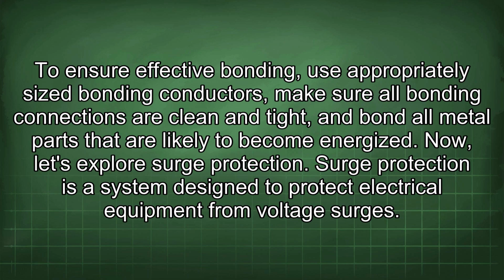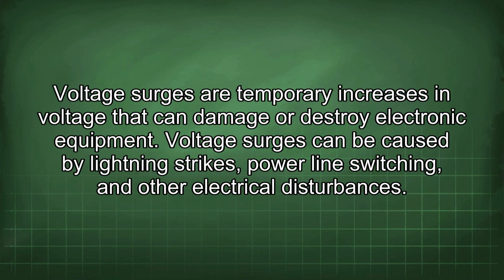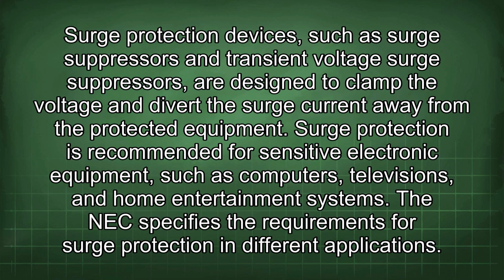Now let's explore surge protection. Surge protection is a system designed to protect electrical equipment from voltage surges. Voltage surges are temporary increases in voltage that can damage or destroy electronic equipment. Voltage surges can be caused by lightning strikes, power line switching, and other electrical disturbances. Surge protection devices, such as surge suppressors and transient voltage surge suppressors, are designed to clamp the voltage and divert the surge current away from the protected equipment.